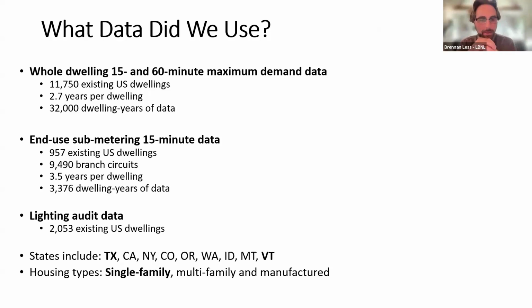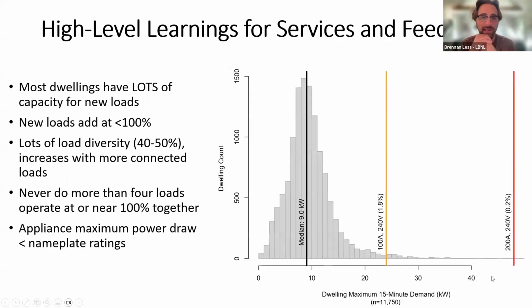I'm probably going to run out of time with these slides, so I'm going to race ahead. But just to say, we used a lot of data to think about this problem. We've got whole dwelling demand data, maximum peak demand data from something like 12,000 US homes, multiple years of data from those homes. We have end use sub-metering data - actual circuit by circuit 15 minute measurements in about 1,000 US dwellings, again multiple years of data. All of this is being leveraged for these efforts to update the code with values that are lined up with what actually happens in homes. Let's jump to the next slide.